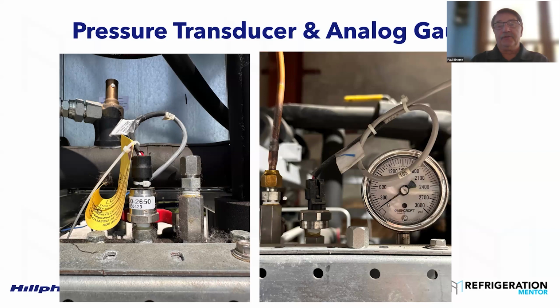Then we're going to go into filling our oil system. When you charge your oil system, you're going to charge your receiver. We don't charge into the compressors like we used to. We're going to fill up our reservoir. We're going to isolate it. Then we're going to put 300 pounds of pressure on it, and then we're going to manipulate the switches and let the compressors fill. And then we're going to let the switches shut themselves off. We want to see that whole system work.